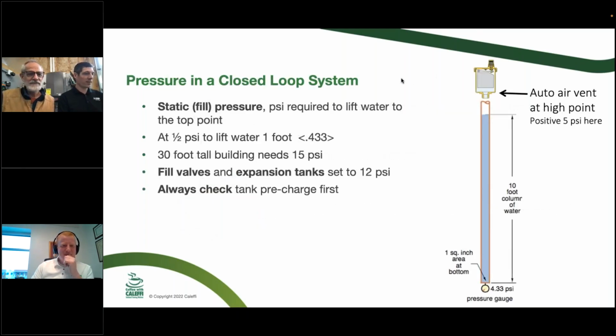So to start with, you want to talk a little bit about pressure in a closed loop system and how a vent works? Yeah, so when we talk about pressure, we're talking about two different pressures in a closed loop system. One is what we call the static fill pressure, and that's the pressure that you get to decide what it needs to be, and it needs to be enough to lift the water up to the highest point in the building. So the number is 0.433 PSI, call it a half a pound of pressure, to lift water up a foot. So if we want to go up 20 feet, use the number.